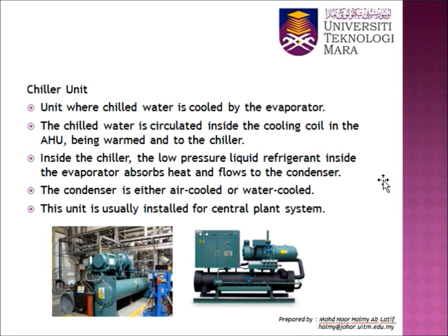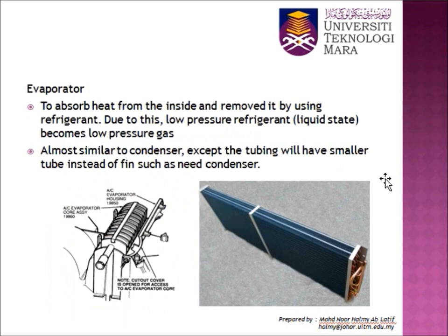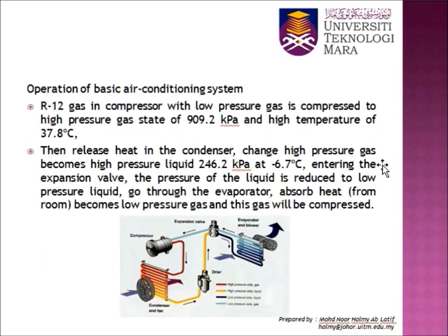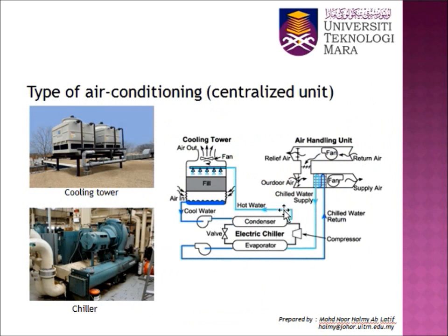Chiller unit. Unit where chilled water is cooled by the evaporator. The chilled water is circulated inside the cooling coil in the AHU, becomes warm and returns to the chiller. Inside the chiller, the low pressure liquid refrigerant inside the evaporator absorbs heat and flows to the condenser. The condenser is either air cool or water cool. This system is usually installed for central plant system. As you can see here, this is what happens in the condenser.